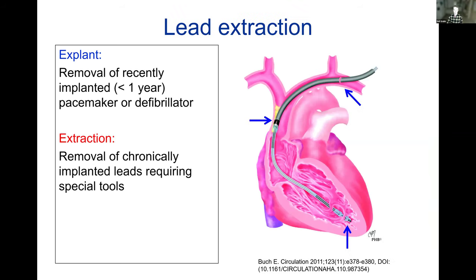Now I'll talk a little about lead extraction for the last part of the talk. First, I want to talk about definitions, because there's a difference between an explant and an extraction. An explant is where, say, you implant a dual chamber pacemaker and six weeks later the patient has a pocket infection — everything needs to come out. You just use local anesthesia, open up, take the pacemaker out, unpick the stitches, and take the leads out, and they will slide out as easily as they went in.